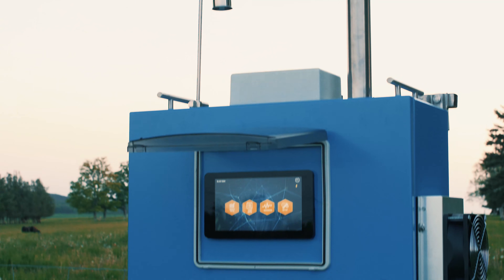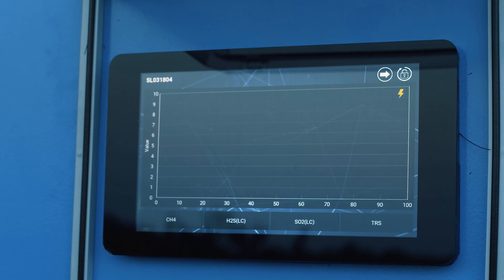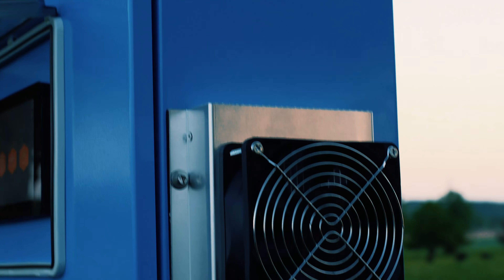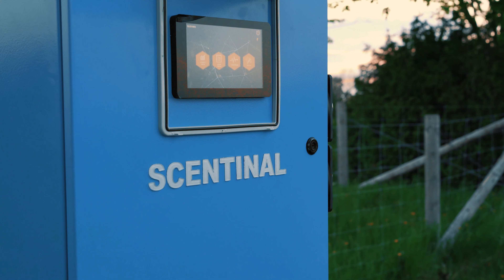Every few hours, the system checks itself against reference gases as per U.S. emission standards. This makes the instrument not only super accurate, but also reliable and virtually maintenance-free. The ability to continuously monitor pollutants from any environment makes it a versatile tool in combating air pollution.